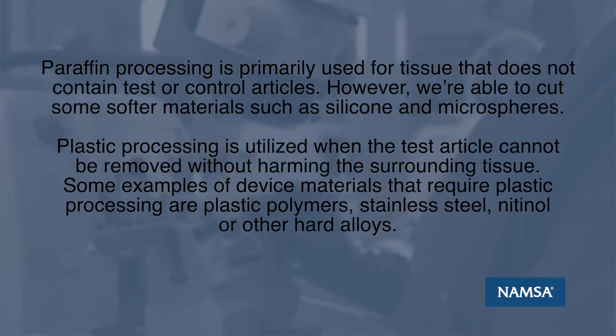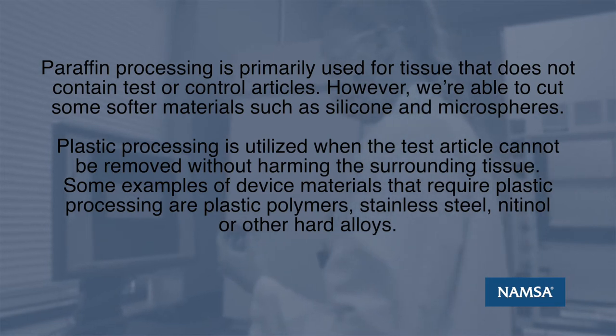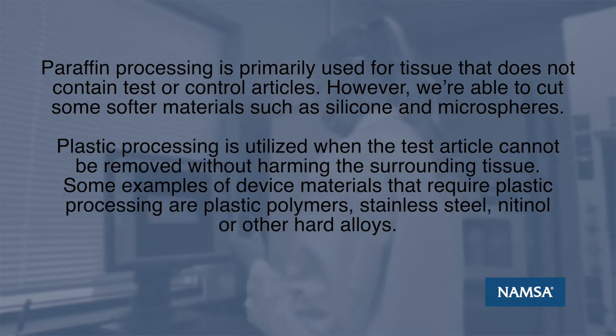Plastic processing is utilized when the test article cannot be removed without harming the surrounding tissue. Some examples of device materials that require plastic processing are plastic polymers, stainless steel, nitinol, or other hard alloys.